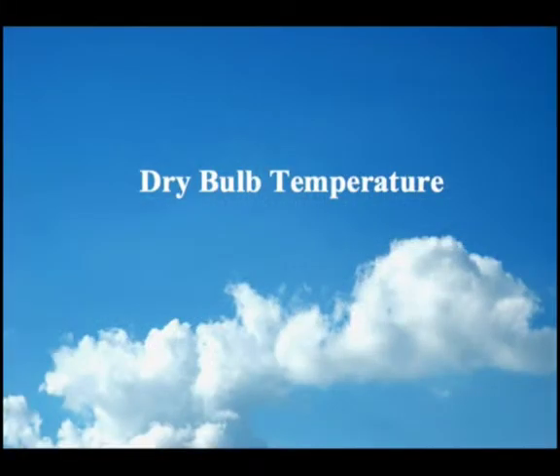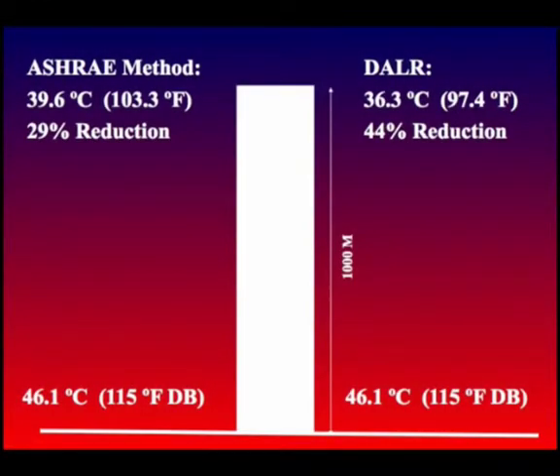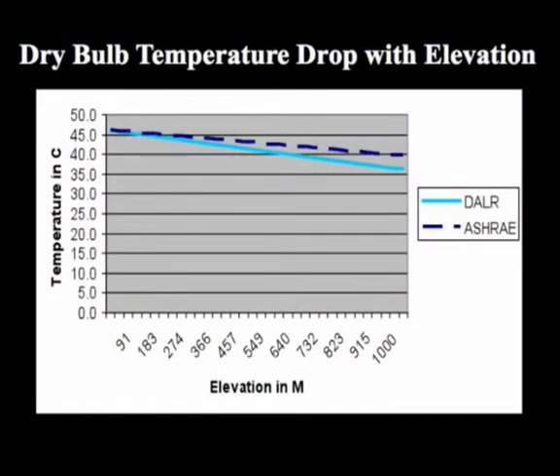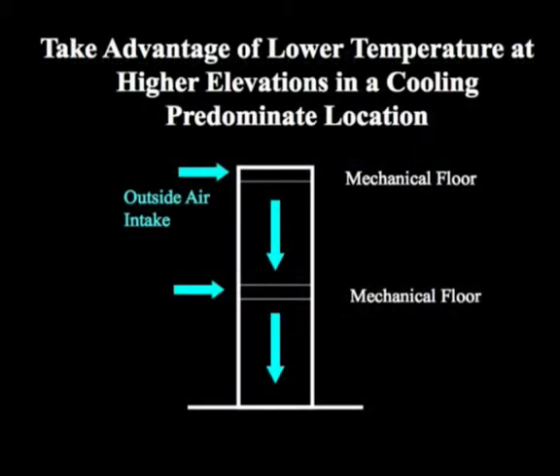Let's look at the first thing, temperature. Most of you know that temperature drops with elevation. If you use the ASHRAE Method, if the ground is at 46.1 degrees Celsius, the top is at 39.6. If you assume the air is relatively dry, then if the ground is 46.1, at the top is about 36.3, a 44% reduction for a 1 kilometer tower right here in Dubai. Those are the chart of the two temperatures. And one way you can take advantage of that, because Dubai is mainly a cooling-predominant climate, is to take advantage of the lower temperature air at the top of the building.